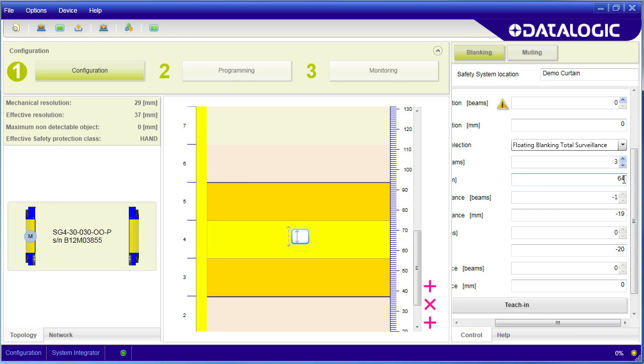You can also tell the sensor that this blanked area can move around or float within the light curtain area. If you use this, you have to make sure the blanked areas never leave the sensor field of view or the outputs will switch.